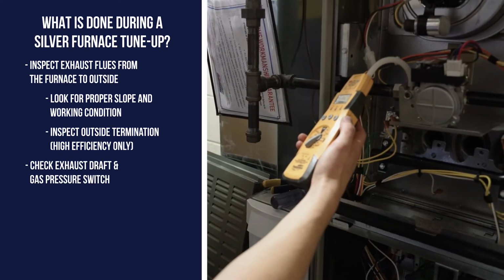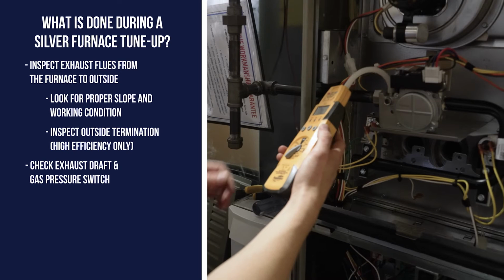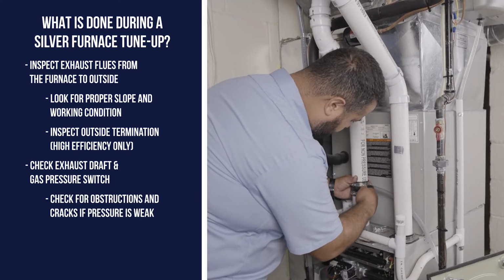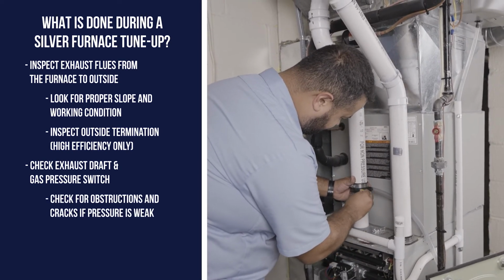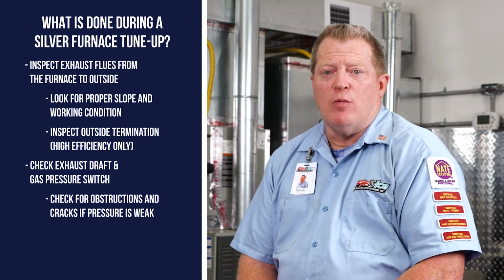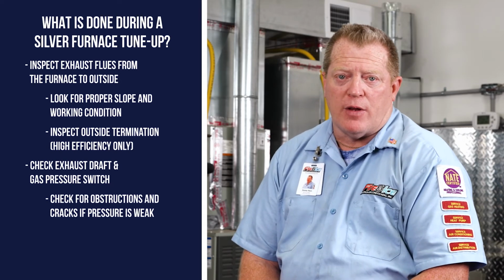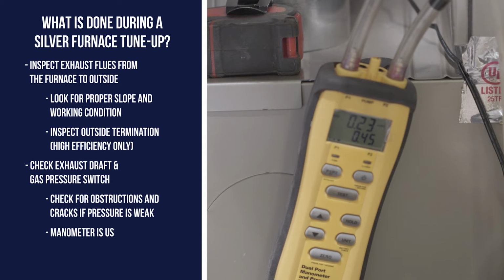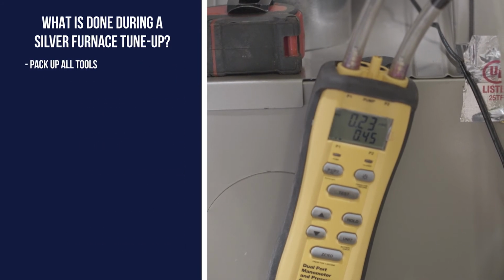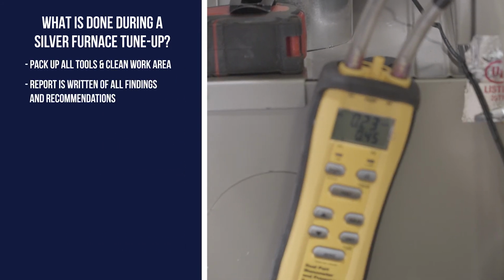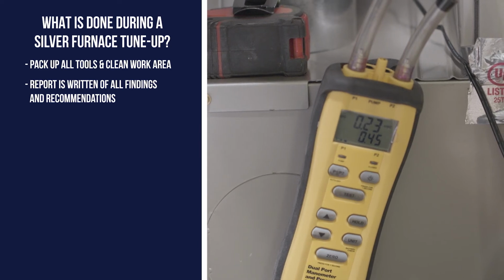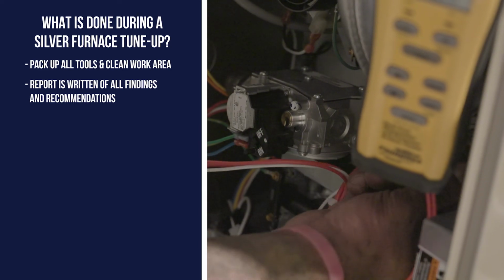Next, we'll turn the furnace back on and check the exhaust draft and pressure switch. If the draft is weak, we check for any obstructions and cracks in the tubing. If the draft is still weak, a recommendation for repair is likely. Next, we turn our attention to the gas pressure. With a manometer, we will ensure the gas pressure to the furnace is within specifications. We'll make the proper adjustments if any are needed.